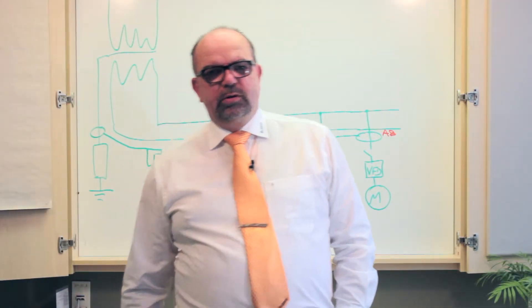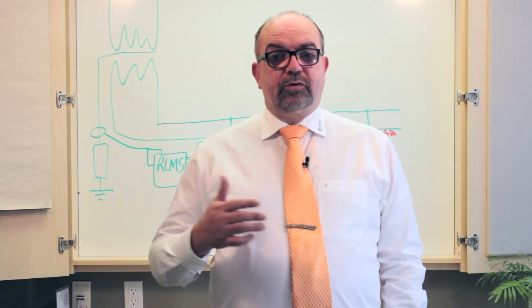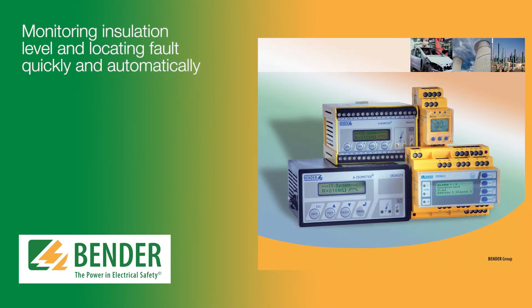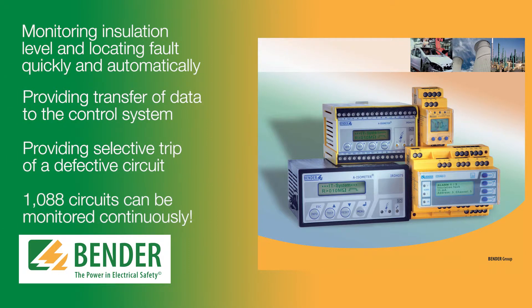Depending on the application, Bender offers two key products for the utility sector. The solution for ungrounded or floating systems is the IRDH575 plus EDS. It's capable of monitoring the insulation level and locating the fault quickly and automatically. It provides transfer of data to the control system and selective trip of a defective circuit. Plus, 1088 circuits can be monitored continuously.